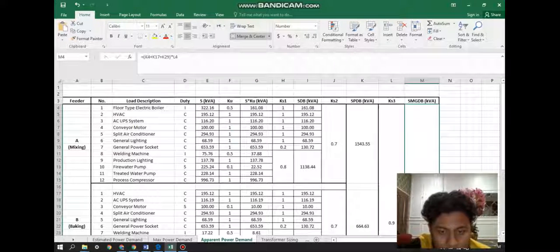Okay. So proceed with this apparent power demand and the appropriate utilization factor, that is KU, and a diversity factor, that is KS, for each load. It must be determined based on the number of hours per day that the load is in operation. So heavy machinery with a high frequency of operation would benefit from an appropriate utilization factor between 1.0 and 0.8. For a much lighter load, a utilization factor of 0.2 might be more appropriate.